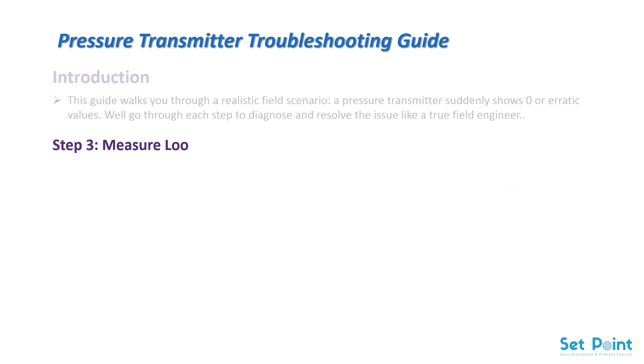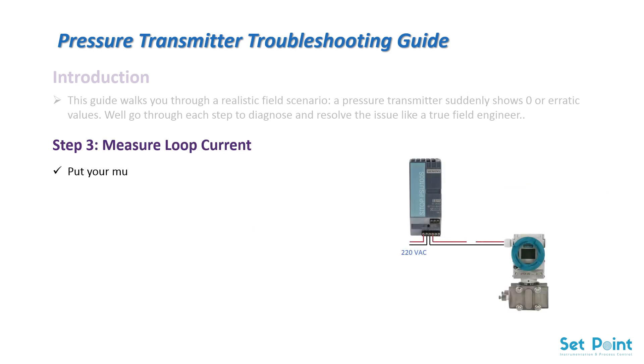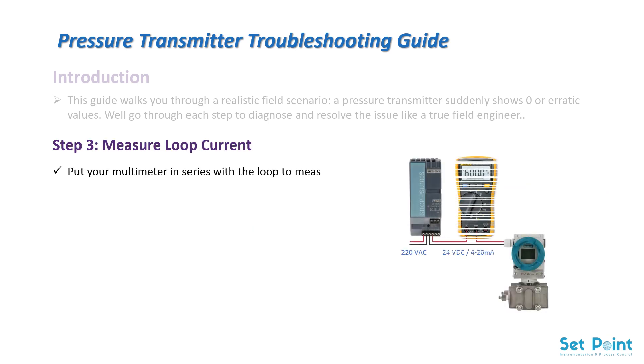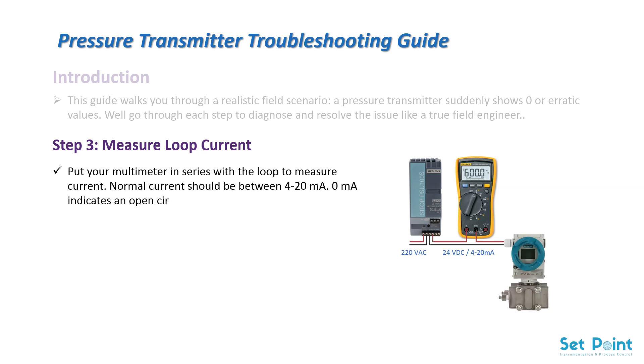Step 3: Measure loop current. Put your multimeter in series with the loop to measure current. Normal current should be between 4 to 20 milliamperes. 0 milliamperes indicates an open circuit; 20 milliamperes constant might mean overrange. Use this as a vital diagnostic indicator.